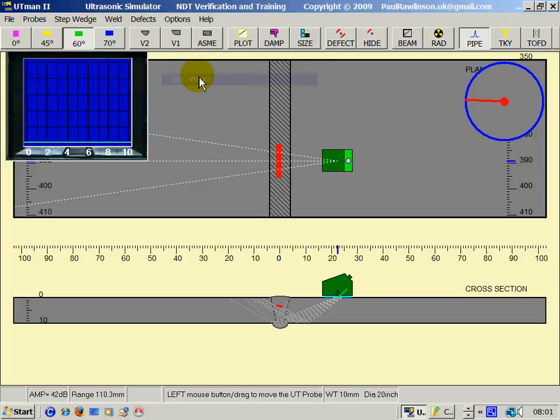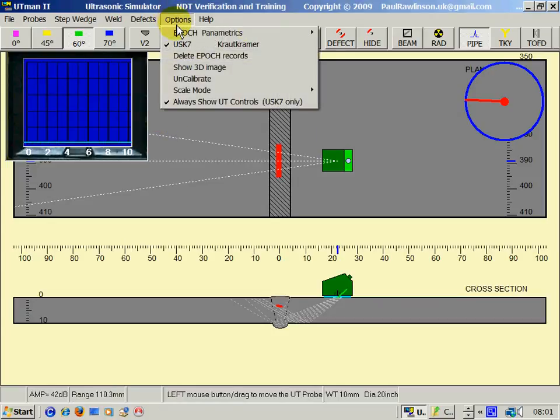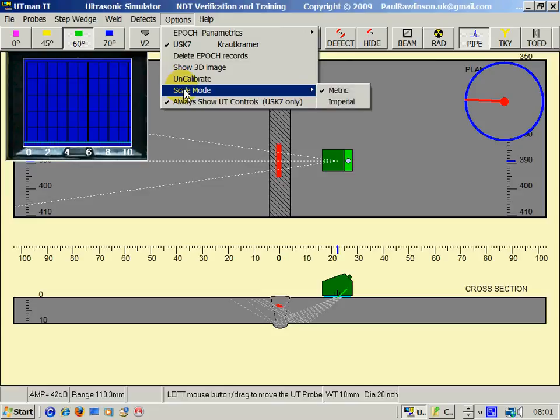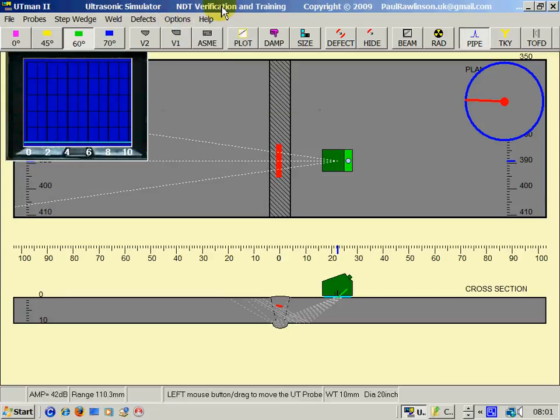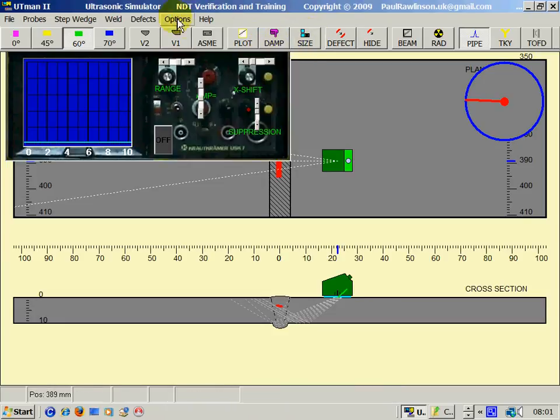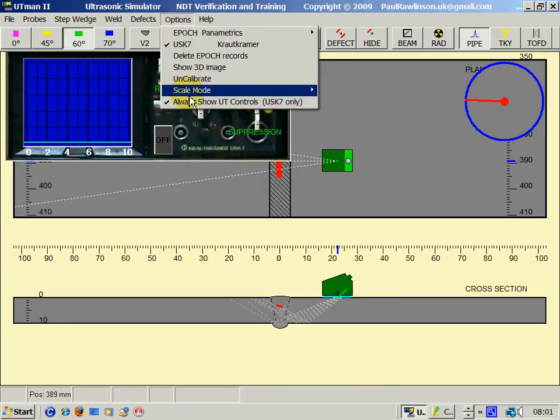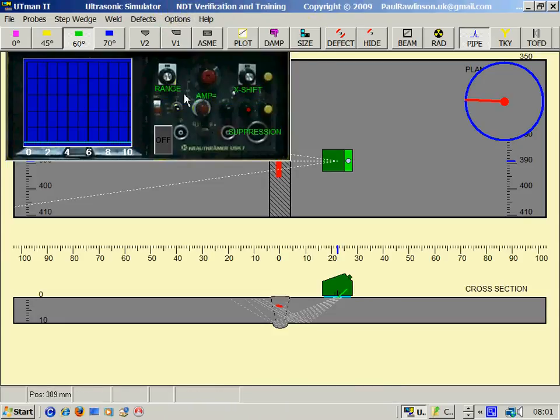Uncalibrate. We'll totally uncalibrate a UT set, so the student can recalibrate it. Scale mode, metric or imperial, and just for the USK7, we can always show UT controls.